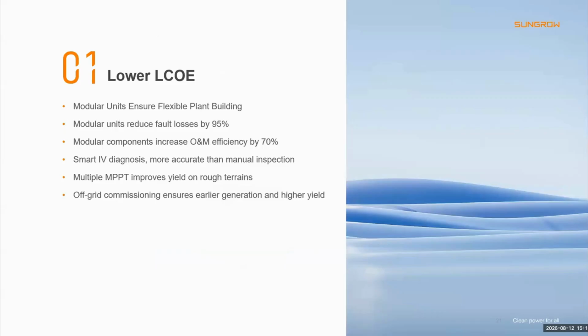For 1 plus X, lower LCOE means several areas. These include flexible plant design, lower fault losses, faster maintenance, smart IV diagnosis, multiple MPPTs, and off-grid commissioning. So the benefit is not just the inverter efficiency. It is a combination of lower capex, higher availability, and better lifetime energy yield.